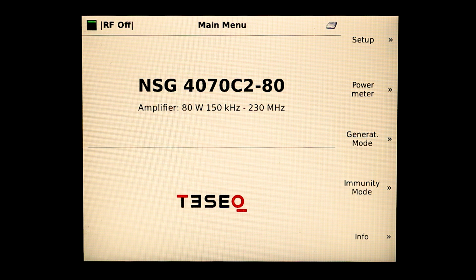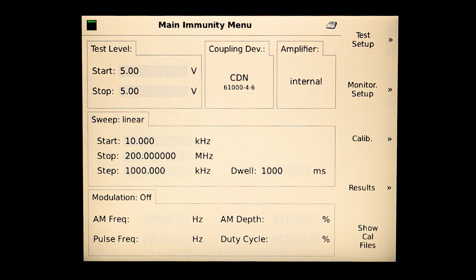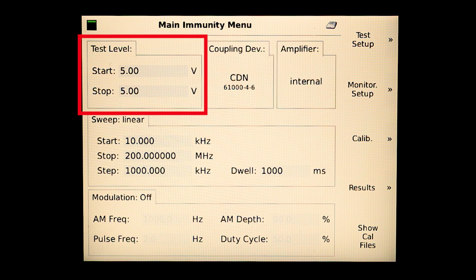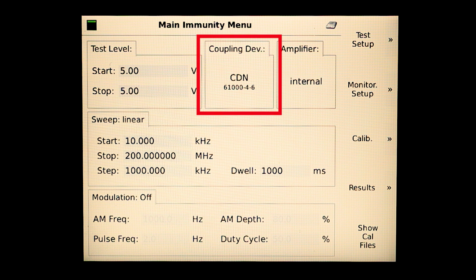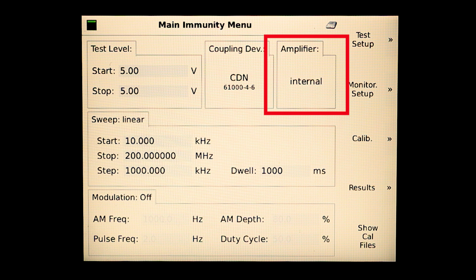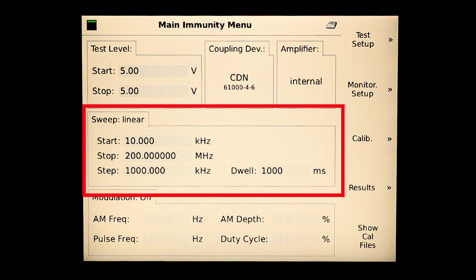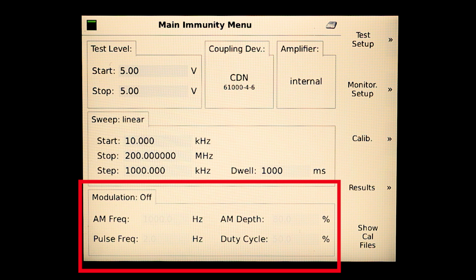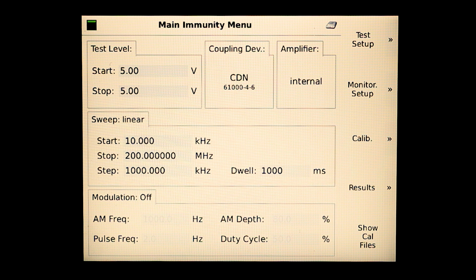Let's click on Immunity Mode. This is essentially going to be the test mode menu. You can see the screen's broken out into a few different sections. In the upper left, we have our test level section, which is currently set at 5 volts. Working our way right, we have our coupling device where we have CDN selected and our IEC 61000-4-6 standard. All the way on the right, we have our amplifier, and just as we mentioned earlier, it is set at internal. Below that, we have our sweep criteria, and then finally, all the way at the bottom, we have the modulation.